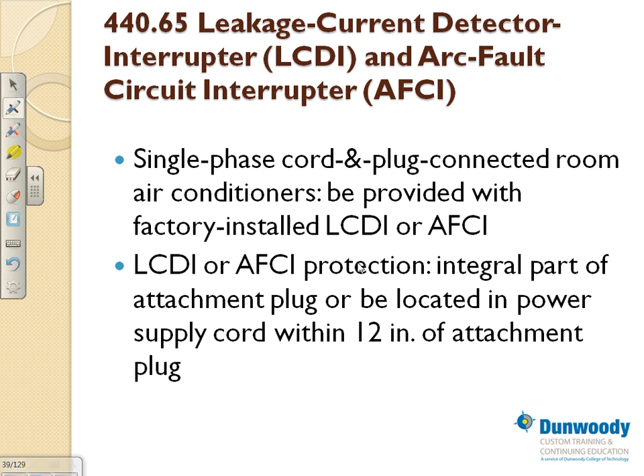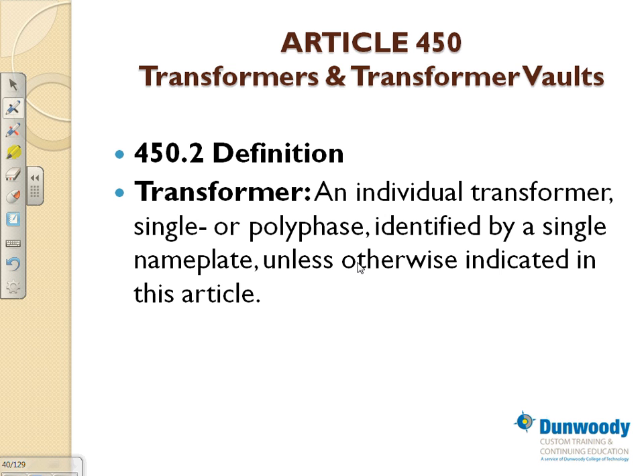Okay, that's all we're going to do. The only thing, guys, is what we highlight is what's important for the journeyman exam. There are a few other things. When I deal with it, you can deal with chillers and compressors. Really, the most important thing on the chiller is the nameplate shows the fuse, stick with the fuse. You have to have a disconnect inside of the equipment. Very important. And also the nameplate shows something called minimum circuit ampacity. Take this to town and go buy the conductor based on 75 degrees and size it if you have to. Transformers. I'm not going to ask you if you guys use transformers.